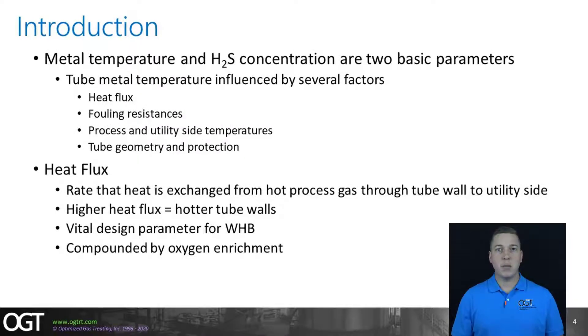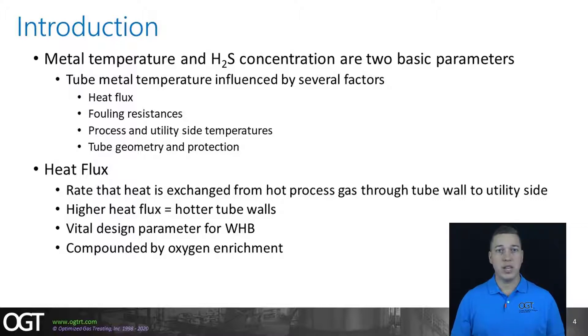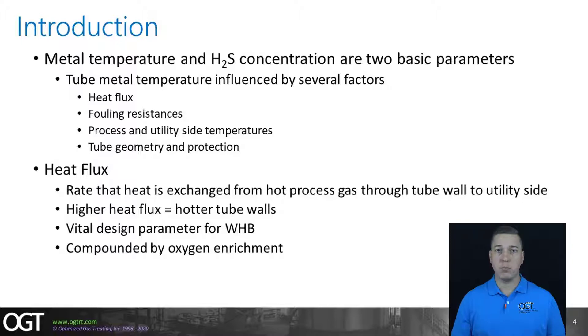Metal temperature and H2S concentration are the two basic parameters that determine the rate of sulfidic corrosion, but there are several factors that go into determining what the tube metal temperature actually is. These factors include the heat flux, fouling resistances, both the process side and utility side temperatures, tube geometry — meaning whether it's a triangular pitch versus a square pitch and how tight those pitches are — along with the protection of those tubes at the front of the waste heat boiler, meaning the refractory and/or ferrules at the tube-to-tube-sheet joint.